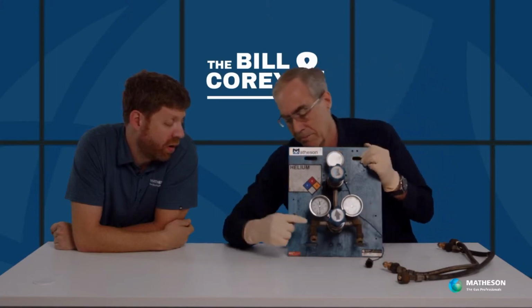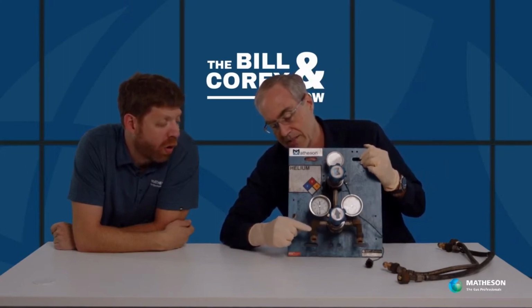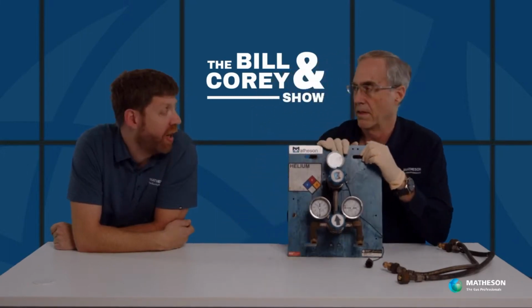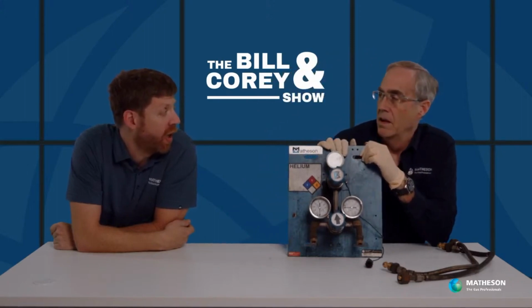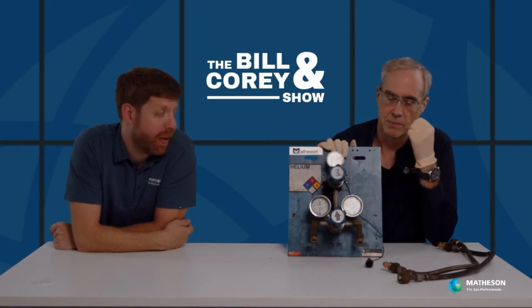This looks like a piece of tubing or something. I was going to say, unfortunately, we can't control what our customers put in there, but always use things that are rated to the proper pressure if you're ever going to put them on. Correct. When you're adding something to your system, you want to check the pressure rating.